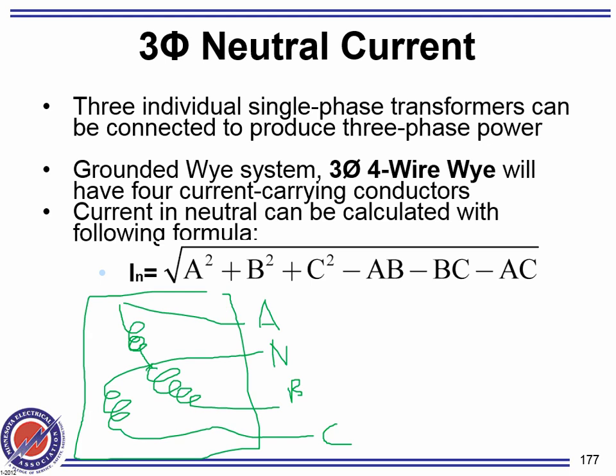You bring a wire here, you ground it. This is called a solidly grounded neutral Y. A solidly grounded Y transformer gets you a solid neutral. Solid ground and gives you a neutral. Okay, if there is no harmonics and you need to find the current that goes through the neutral, the current that goes through neutral will be a function of all the others.